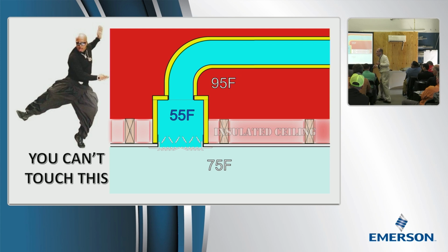Return air duct would probably be okay buried. The problem is burying 50 to 55 degree air in 80 degree dew point fluffy stuff, unless it has R14 non-permeable, then we don't care what you do. Otherwise, don't do it. My recommendation for climate zone 2 as well: don't do buried ducts. I don't recommend it in Florida.